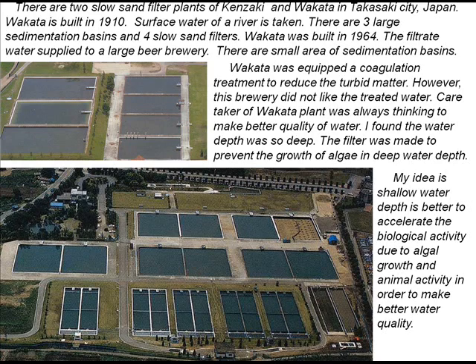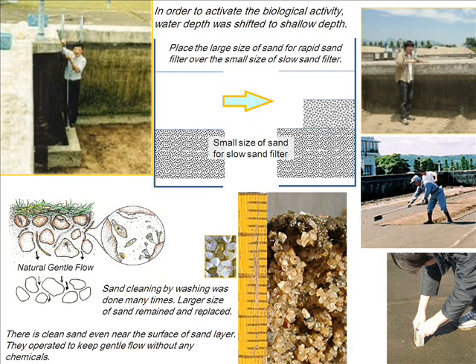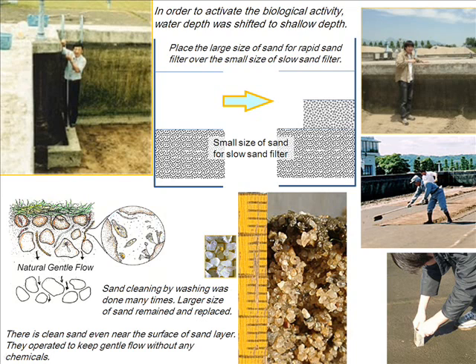My idea is that shallow water depth is better to accelerate biological activity due to algal growth and animal activity, in order to make better water quality. In order to activate the biological activity, water depth was shifted to shallow depth. When the total depth of the sand layer became large, filter resistance might be larger than the ordinary sand layer. In order to reduce the effect of filter resistance, large sizes of rapid sand filter were placed over the sand bed.